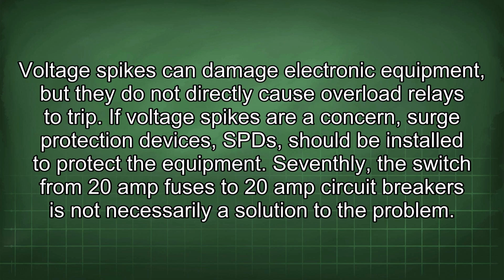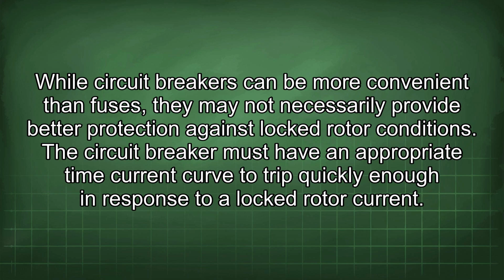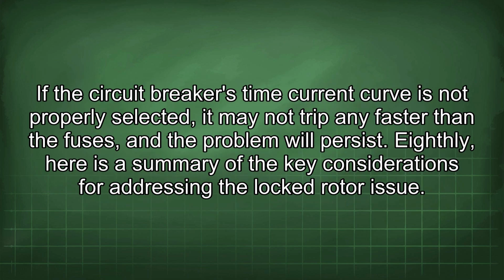Seventhly, the switch from 20 amp fuses to 20 amp circuit breakers is not necessarily a solution to the problem. While circuit breakers can be more convenient than fuses, they may not necessarily provide better protection against locked rotor conditions. The circuit breaker must have an appropriate time current curve to trip quickly enough in response to a locked rotor current. If the circuit breaker's time current curve is not properly selected, it may not trip any faster than the fuses, and the problem will persist.